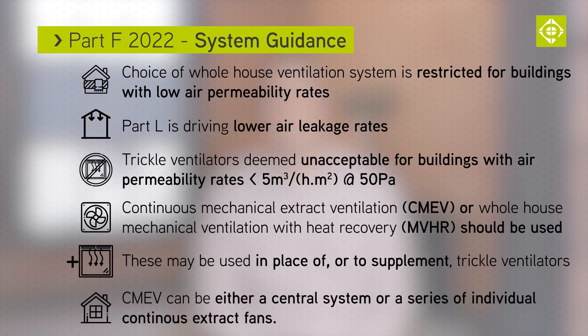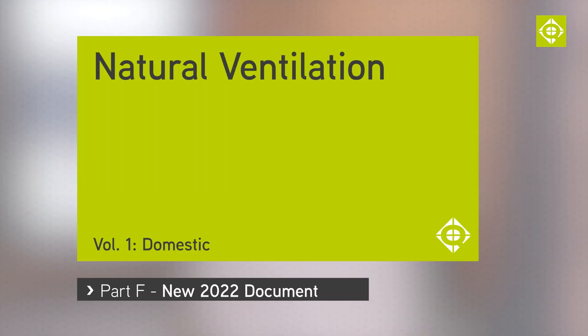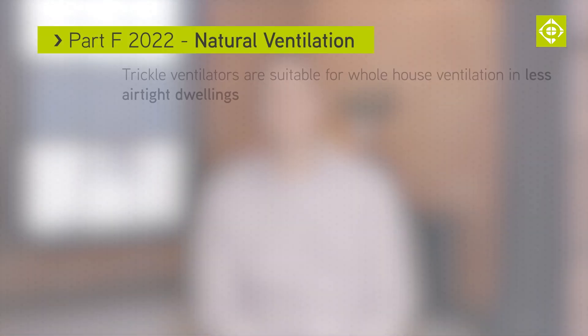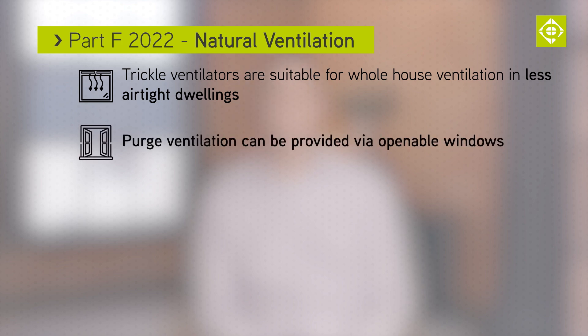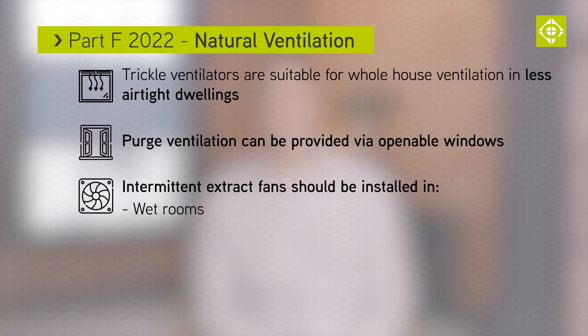Continuous mechanical extract ventilation can be a centralised system or a series of individual continuous extract fans in place of intermittent extract fans. For less airtight dwellings, whole house ventilation can be achieved using trickle ventilators rather than continuous mechanical extract ventilation. Purge ventilation can be provided by openable windows. Intermittent extract fans should be provided to wet rooms, utility rooms, bathrooms, kitchens and sanitary accommodation.